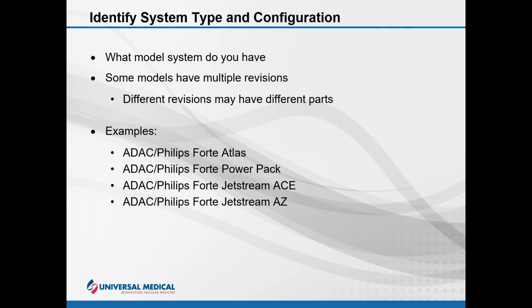Let's use the ADAC Philips Forte, for example. The Forte Atlas is the first example of this system. With this model, much of the electronics are contained in a standalone cabinet called the Atlas. It was a short time later they released the Forte Power Pack. This is essentially the same camera with different packaging. The Power Pack, as it's termed, uses the available space in the back of the camera gantry to house all the electronics that were previously contained in the separate Atlas cabinet. Although most of the components are the same between the Atlas and the Power Pack, there are a few that are different. Most notable differences would be additional power supplies and moving the gantry PC portion into the Power Pack itself.